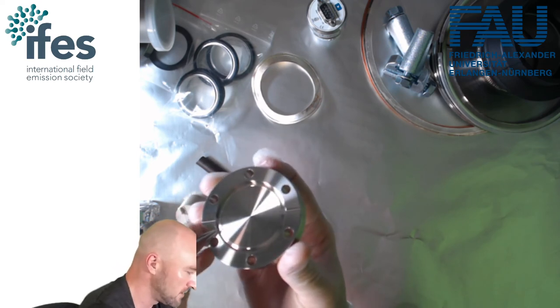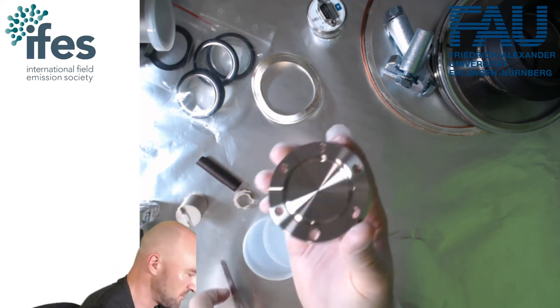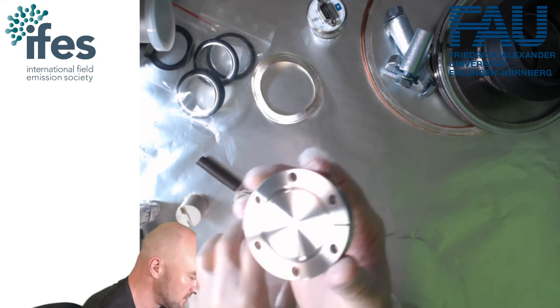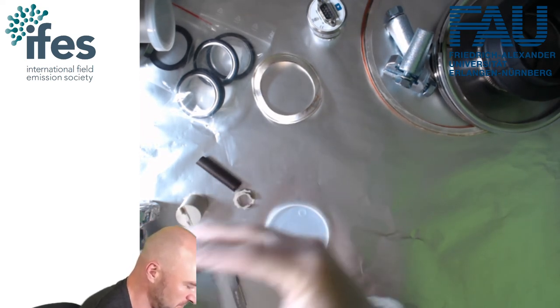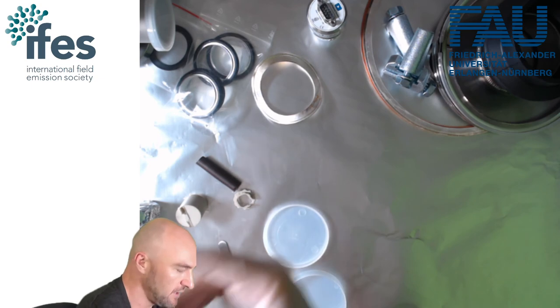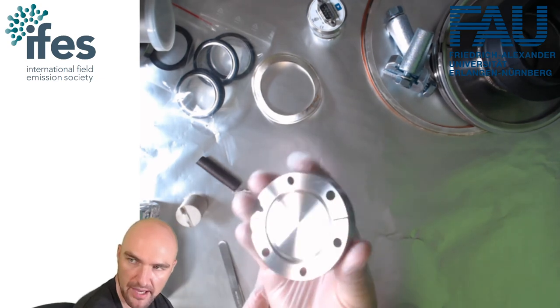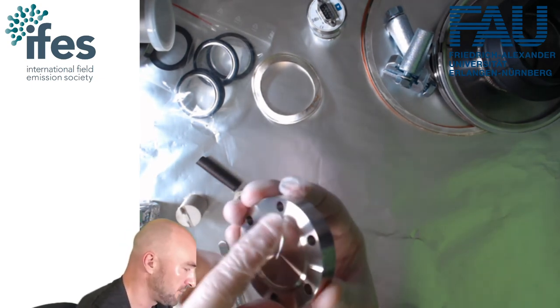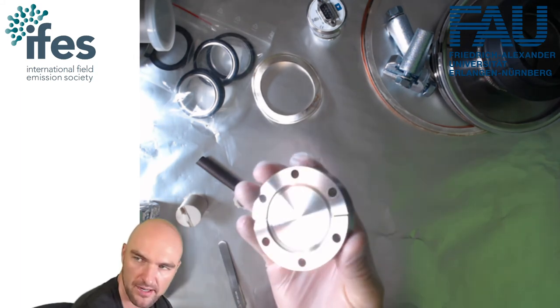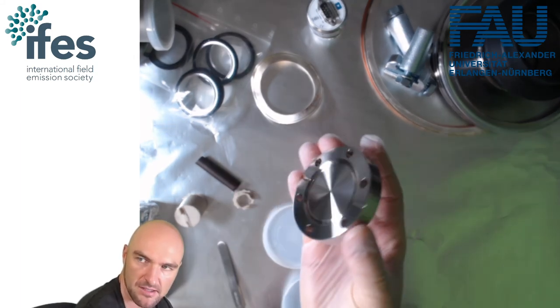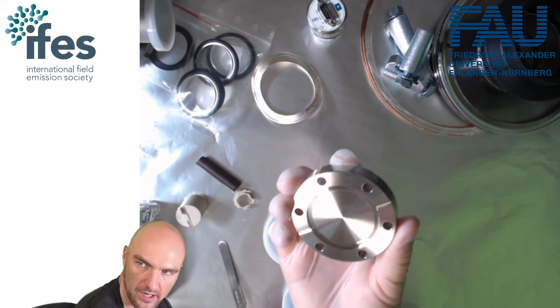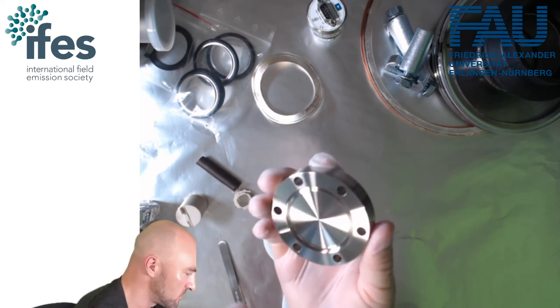Let me just point you there a bit more. So this here, this is the knife edge. And the knife edge, as it sounds, is supposed to be as sharp as possible. This means that if we deal with those flanges, we need to take a lot of care to not damage the knife edge. So if you create a nick in there, then the sealing action would not properly work anymore. It really needs to be very, very sharp.